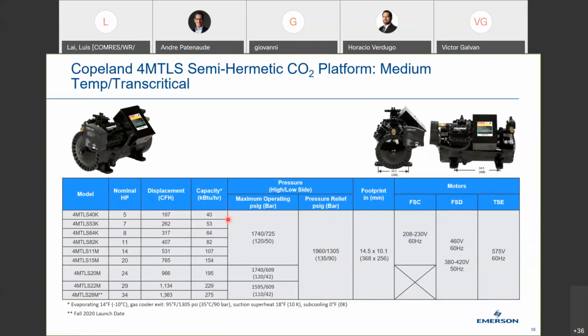These models from 40,000 to 154,000, actually all the way to 195,000, have a pressure rating of up to 120 bar or 1,740 pounds. That's pretty high. In really high ambient regions, they can actually work pretty close to those ranges. They have pressure reliefs of 135 bar or almost 2,000 pounds. That pressure relief in the front here, 135 bar pressure relief. With the largest displacements, the maximum operating discharge pressure is a little bit lower. It's around 1,600 pounds. But the pressure reliefs are all the same.